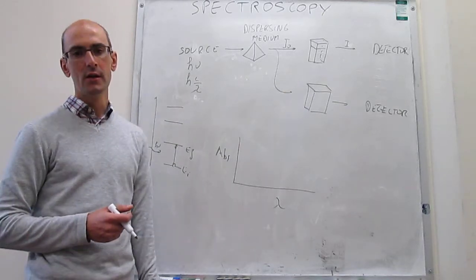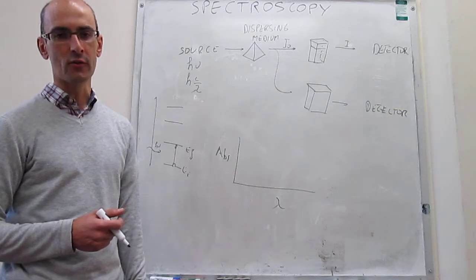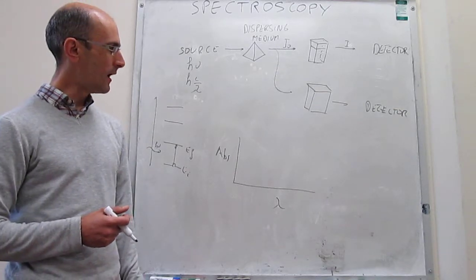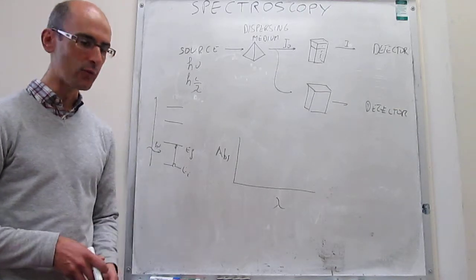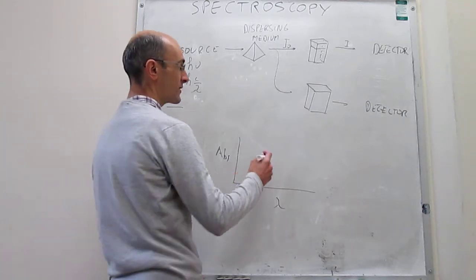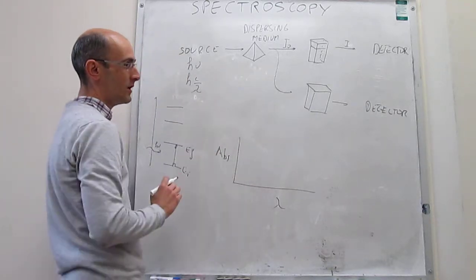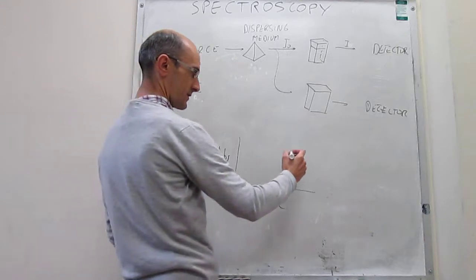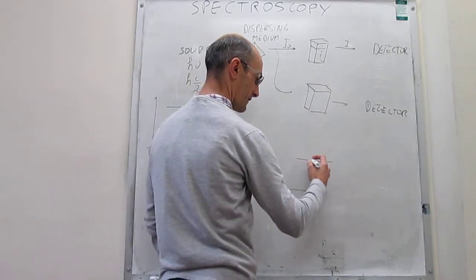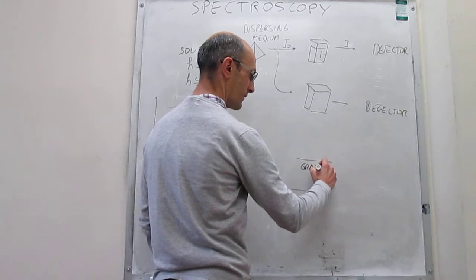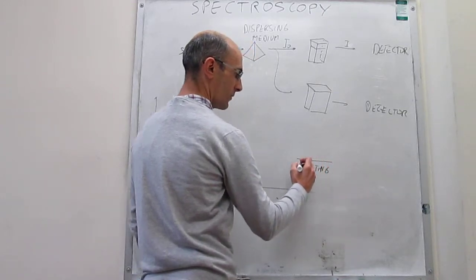In more modern times, we use something called a diffraction grating to select different wavelengths. And the way that diffraction gratings mounted on the spectrometers work is as follows. This is the grating, and this grating has grooves.